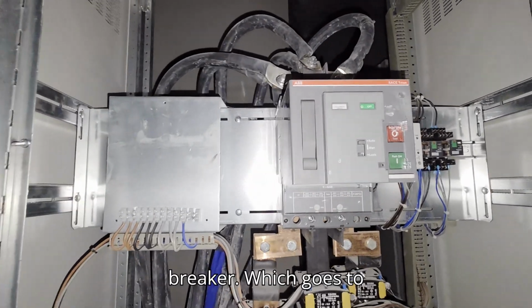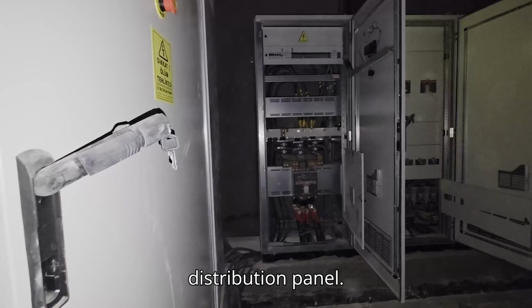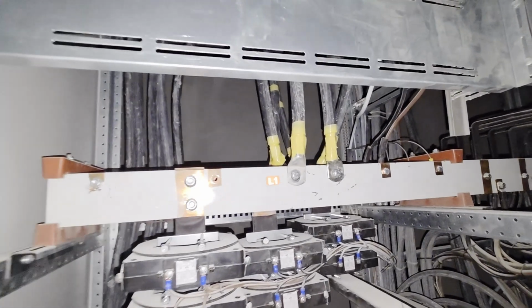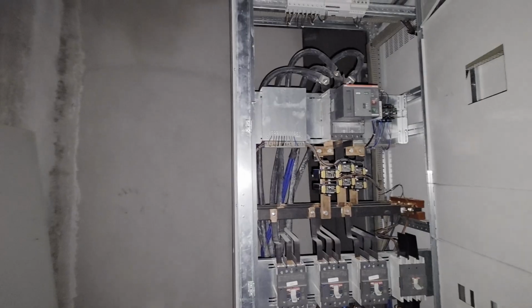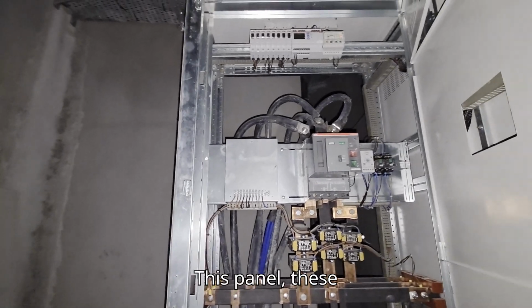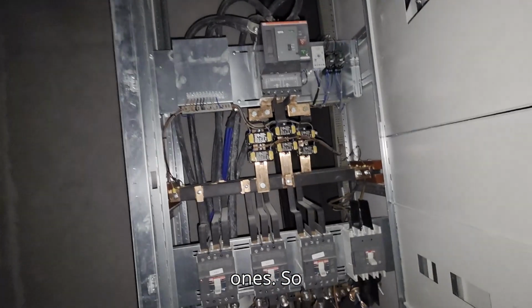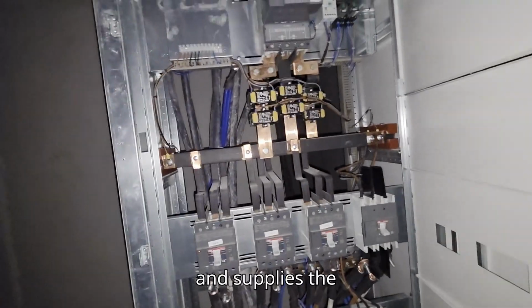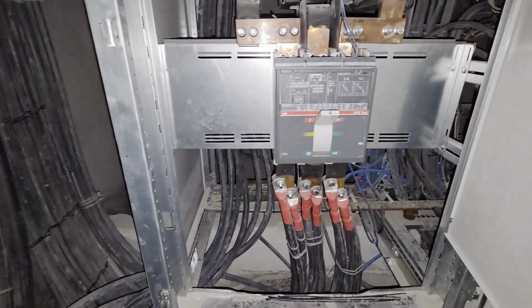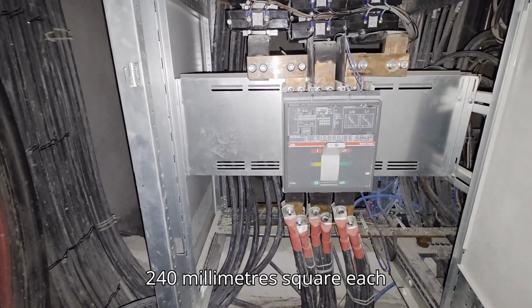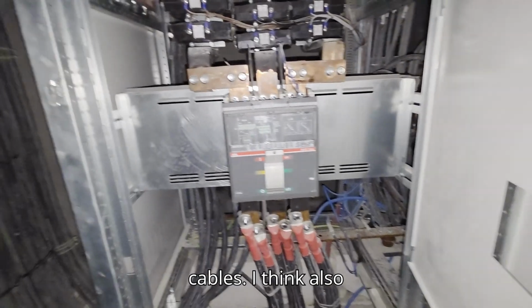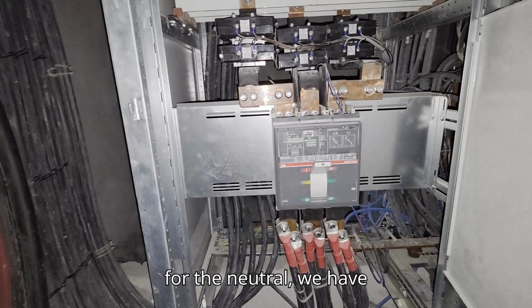So basically this is the main circuit breaker which goes to the main distribution panel. These cables, the ones that are taped with yellow, are the cables that are coming from this panel, these ones. So basically energy comes from the inverter and supplies the load directly. These cables are coming from the transformer directly, 240 millimeters square each one of them. For each phase we have 4 cables. I think also for the neutral we have either 4 or 2, I'm not very sure.